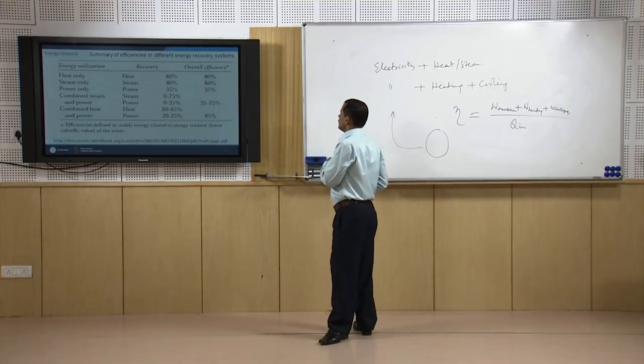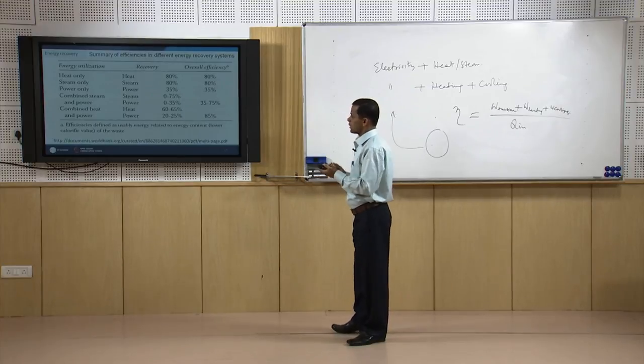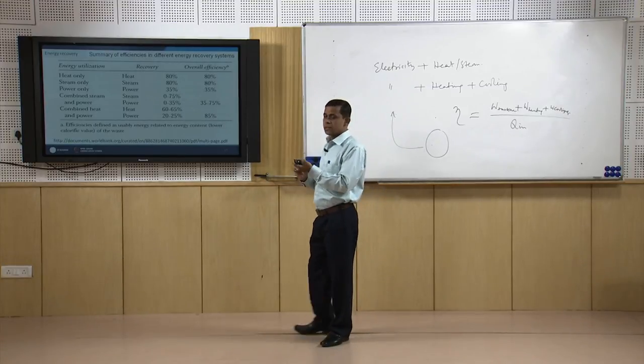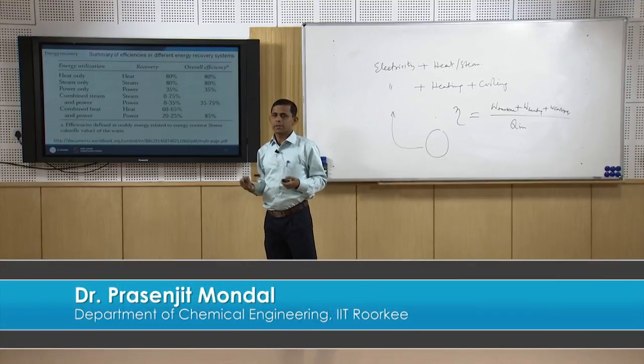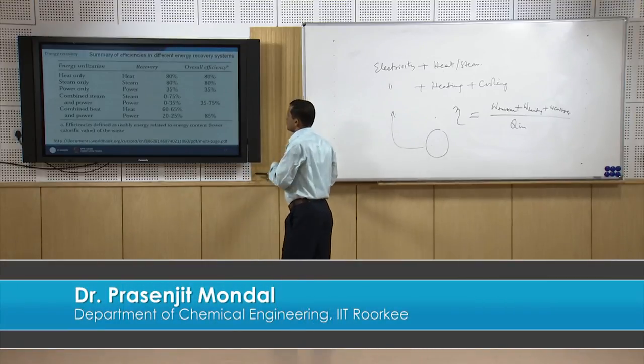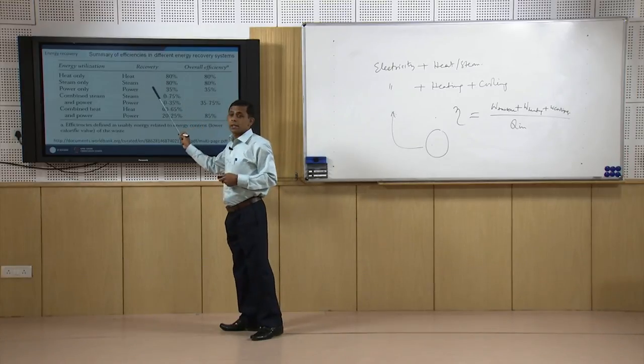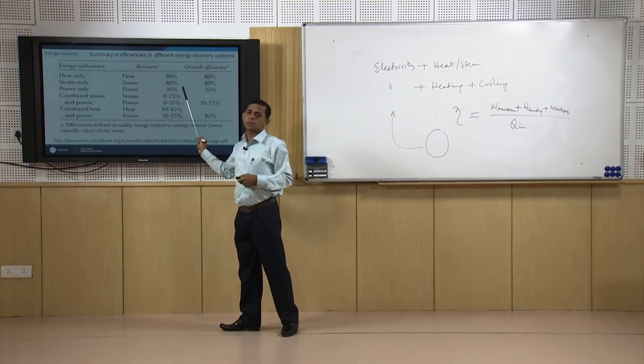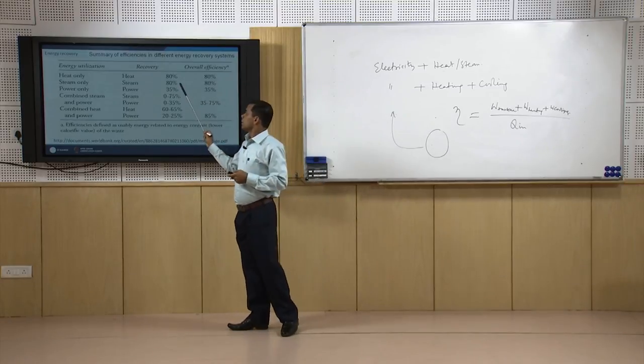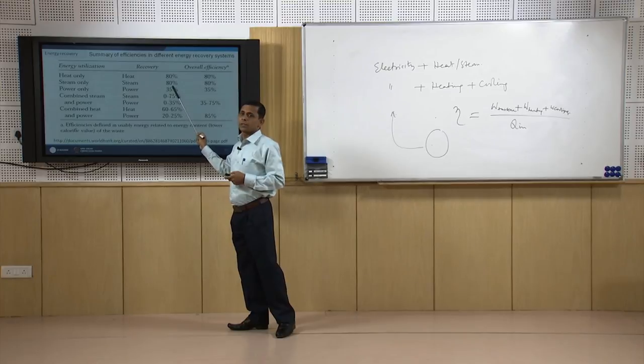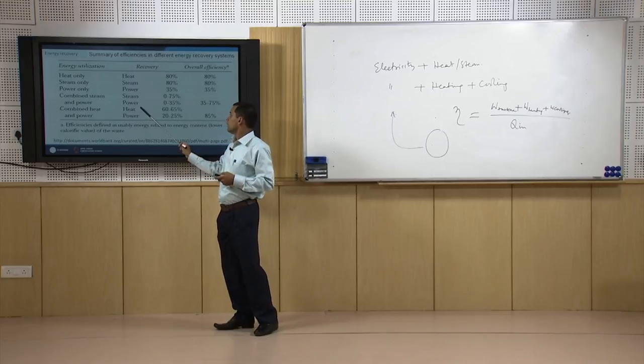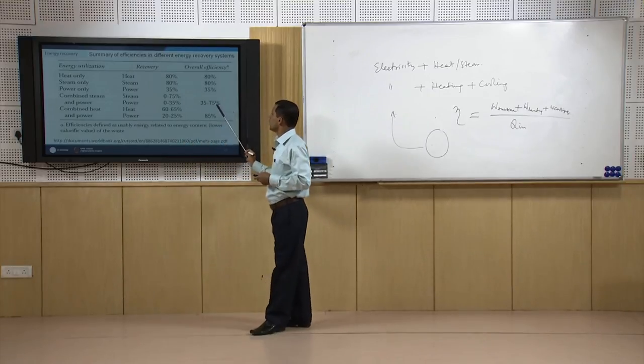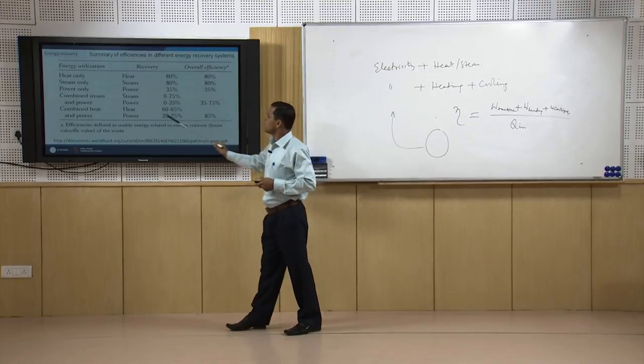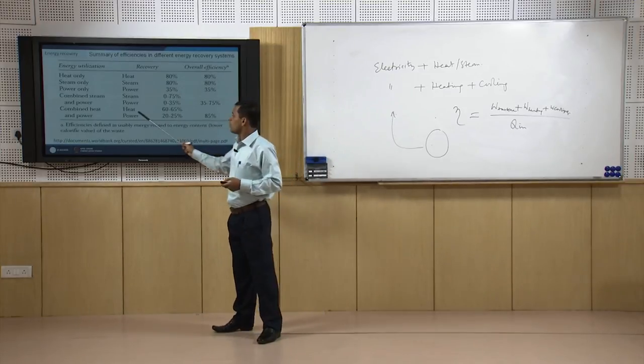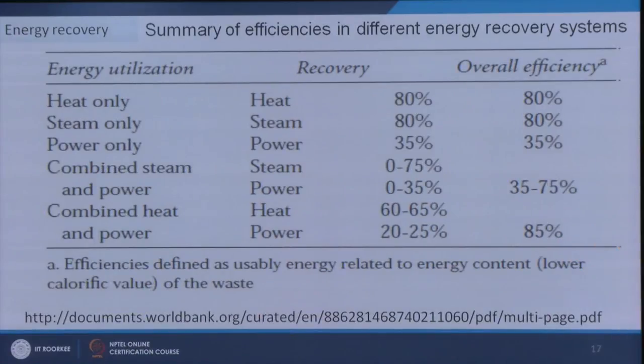This is an example of how combining steam generation, heat generation and electricity generation improves efficiency. Heat production alone can reach maximum 80%, steam 80%, but power alone is only about 35% efficiency. Steam and heat separately give more efficiency, but if you combine them - steam and power, or heat and power - you get intermediate overall efficiency, and the maximum efficiency is achieved with combined heat and power.